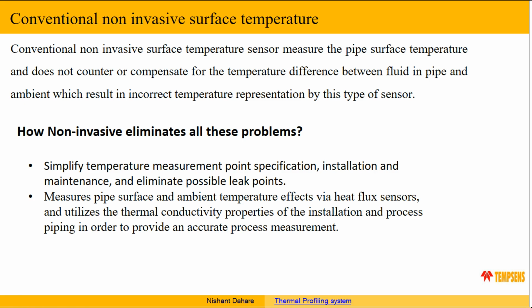Surface temperature sensors, as I mentioned, have inaccuracies due to improper compensation of ambient temperature. Our sensor comprises two things: heat flux sensors and an RTD. I'll give you a brief idea of how this sensor works and how it gives an accurate temperature of the fluid inside the pipe without any intervention, drilling, or hole - you just stick it on the pipe and get the exact internal temperature.